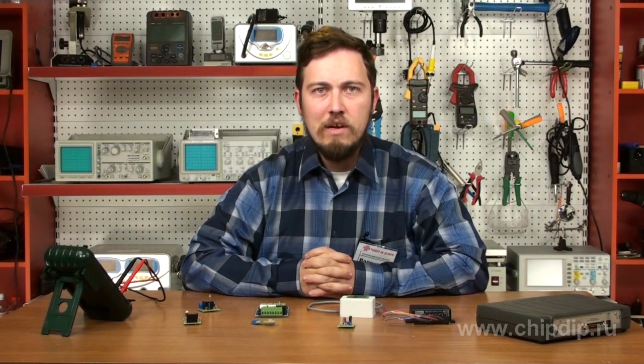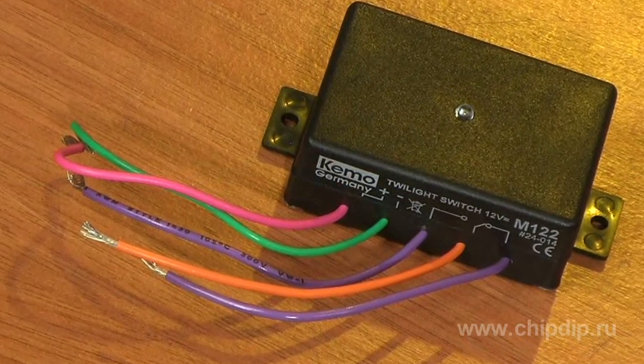To automate the switching on and off of the nighttime lights in the hall in the entrance of an apartment house or of the night side street lights, we can use a twilight switch. The M122 model operates using the voltage of 12 volts. It is small in size, has high reliability and generates no noise on the mains. The module does not respond to short-term changes in lighting, that is, from headlights of passing cars, as it has the built-in delay device from 3 to 4 seconds.